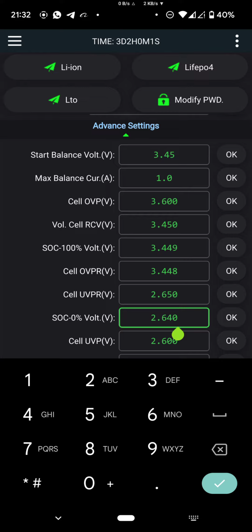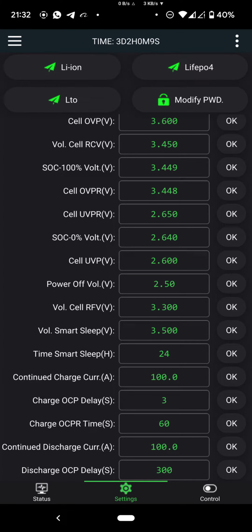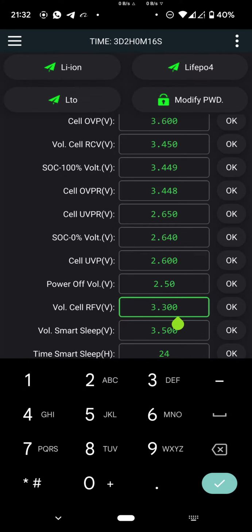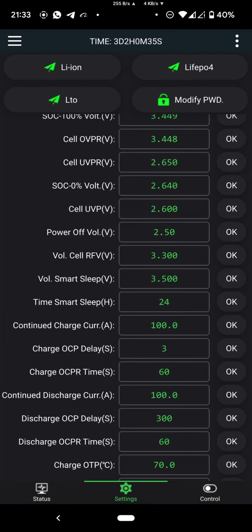Another new parameter is SOC0. So when this voltage is reached by any of the cells, the state of charge is set to 0. No need to change this. Another new parameter is voltage cell RFV. So this is the floating voltage. This value times 16 is requested by the BMS for the floating voltage. I will get to this later, but usually I set it to 3.3 or 3.35.